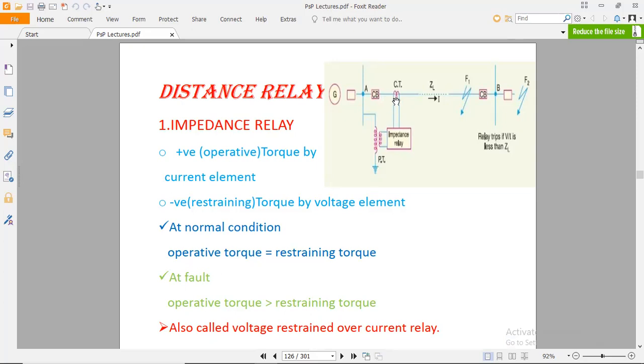If an abnormality is produced in the power transmission line, then the current will exceed its permissible limit as provided by the user defined value. So all the parameters can be fulfilled. The impedance of the line is also fed here, and if its parameters change to different values, then the fault and the impedance of the power transmission line will change, and this can also be observed by the impedance relay.